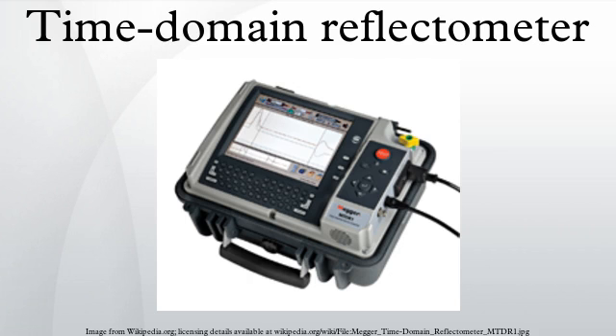A TDR transmits a short rise time pulse along the conductor. If the conductor is of a uniform impedance and is properly terminated, the entire transmitted pulse will be absorbed by the far end termination and no signal will be reflected toward the TDR. Any impedance discontinuities will cause some of the incident signal to be sent back towards the source. This is similar in principle to radar. Increases in the impedance create a reflection that reinforces the original pulse, whilst decreases in the impedance create a reflection that opposes the original pulse.